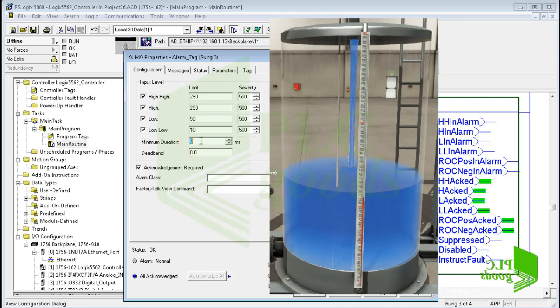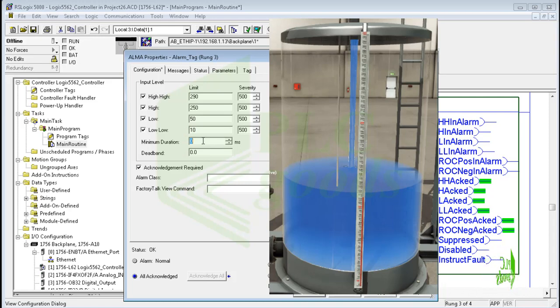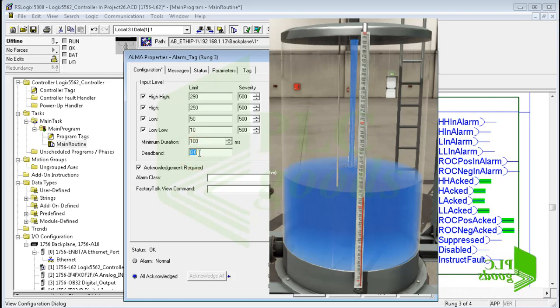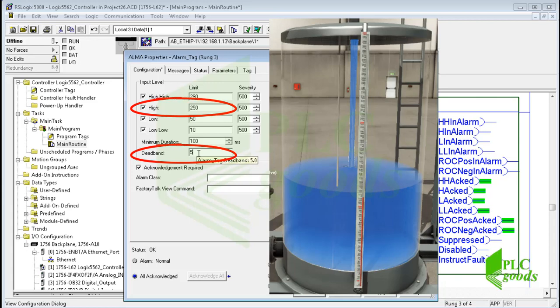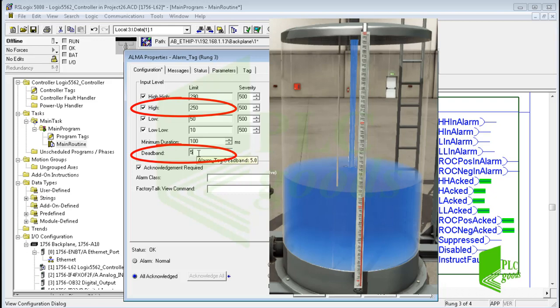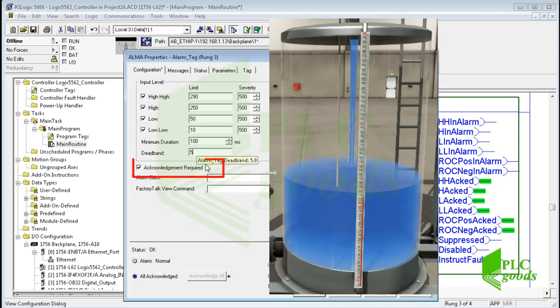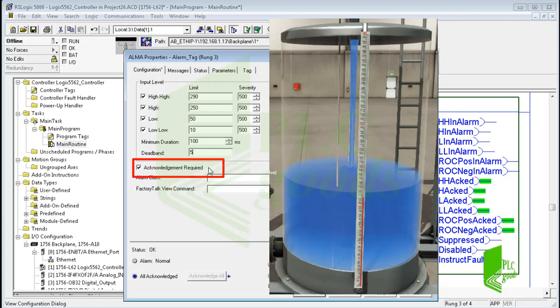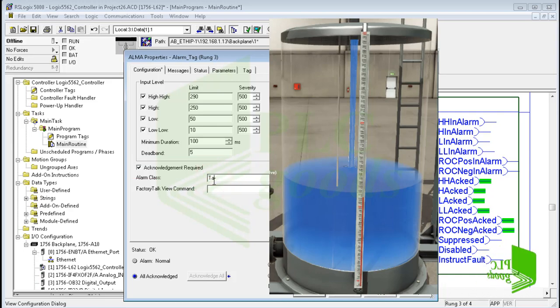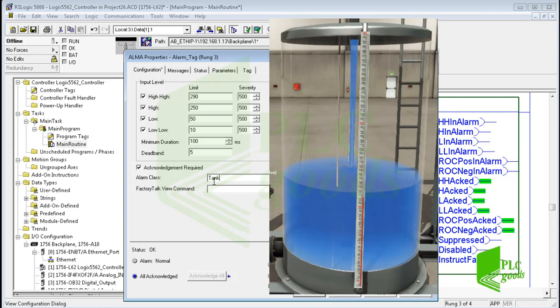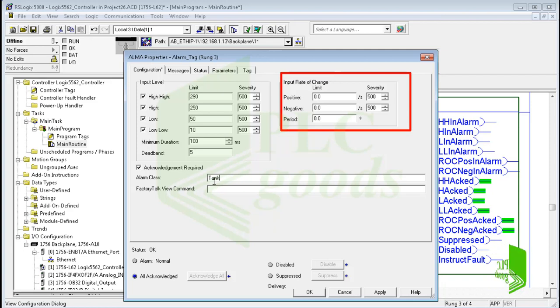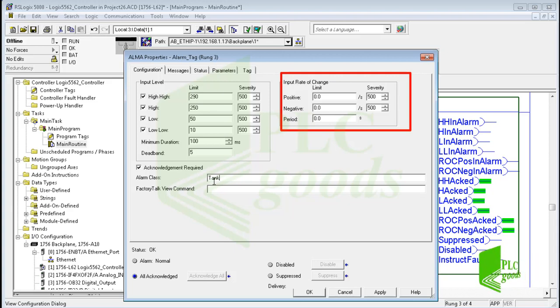Then I can enter the length of time that the alarm condition must be detected before the alarm is reported. After that, a dead band can be entered that applies to all level conditions. For example, based on these values, if the water level exceeds 255, the related alarm will be activated, and if the level is reduced to 245, the related alarm will be cleared. Here we can check this box to require acknowledgement of all conditions for this alarm. Also we can use the alarm class to group related alarms. For example, specify class tank to group all the tank alarms, or specify class control loop to group all alarms for PID loops. On the right side, we can determine rate of change limits in two directions, positive and negative. Sometimes the level changing rate is more important than the level.